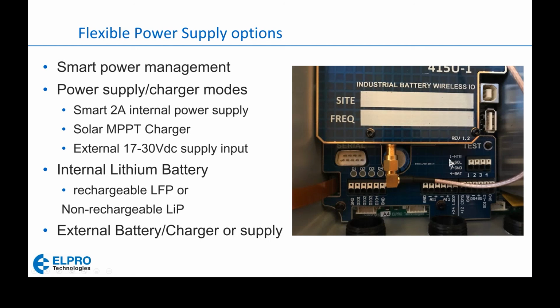And lastly, we do have the option of a heater if you need it, if you're way up north, and we decide we need to heat the enclosure just a tiny fractional amount, just to make sure the battery doesn't get too cold and lose its capacity. So we also have that capability, and this would only be used in extreme cases—we're talking Arctic Circle is when we'd actually need to use that heater.